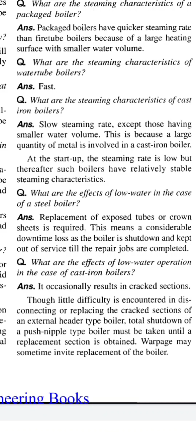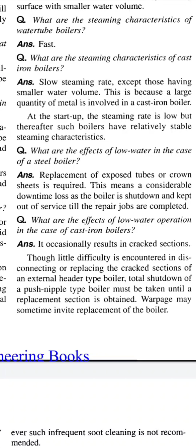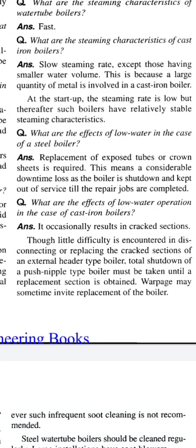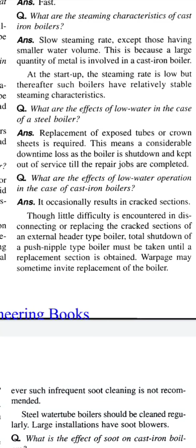Question: what are the effects of low water operation in the case of cast iron boilers? Answer: it occasionally results in cracked sections, though little difficulty is encountered in disconnecting or replacing the cracked sections of an external header type boiler. Total shutdown of a push nipple type boiler must be taken until a replacement section is obtained. Warpage may sometimes invite replacement of the boiler.